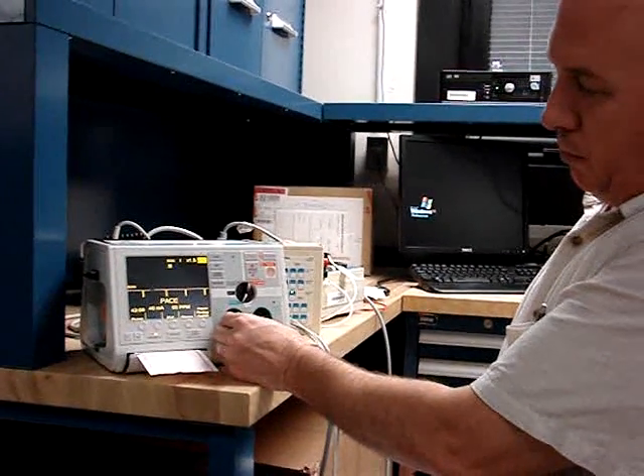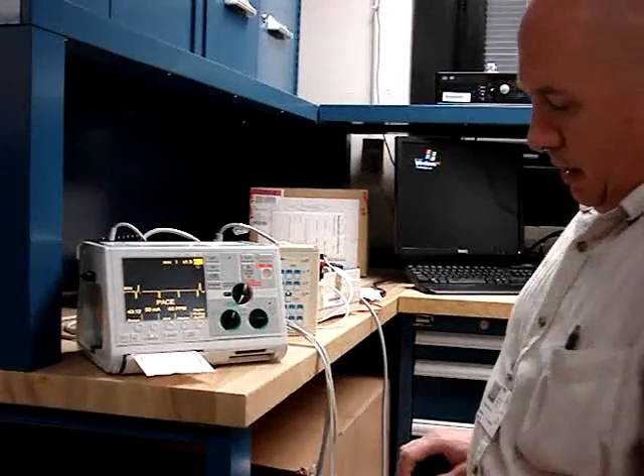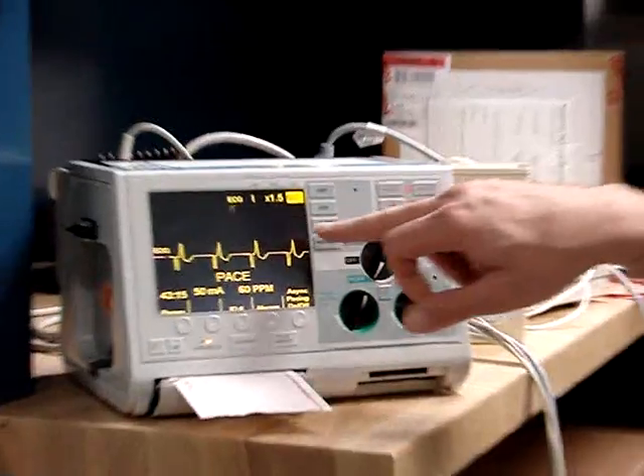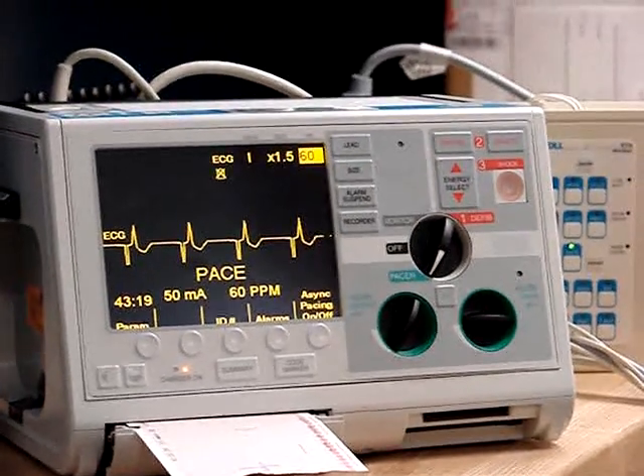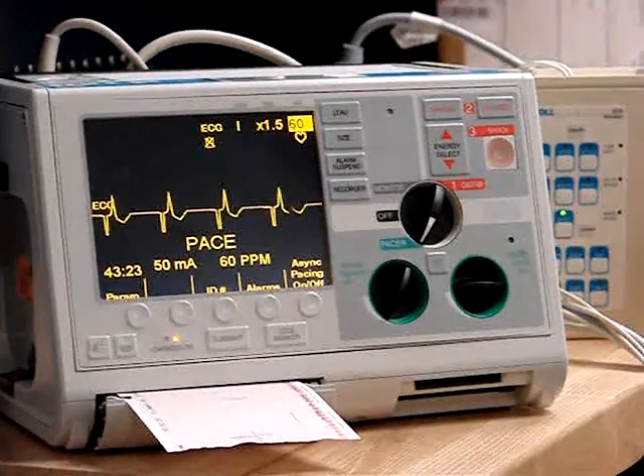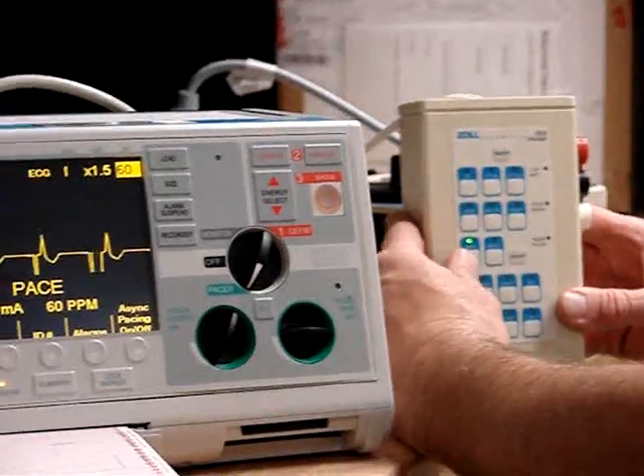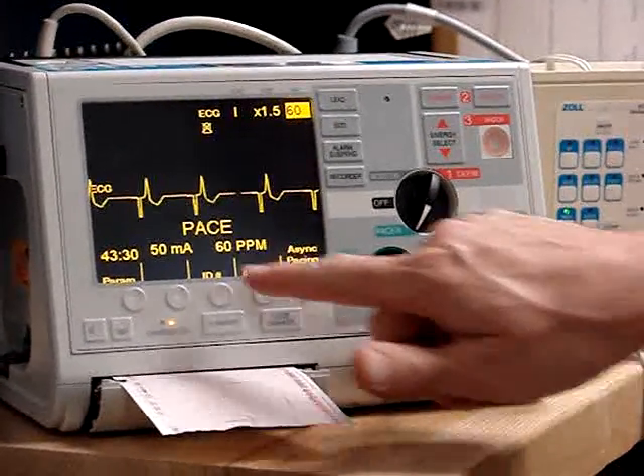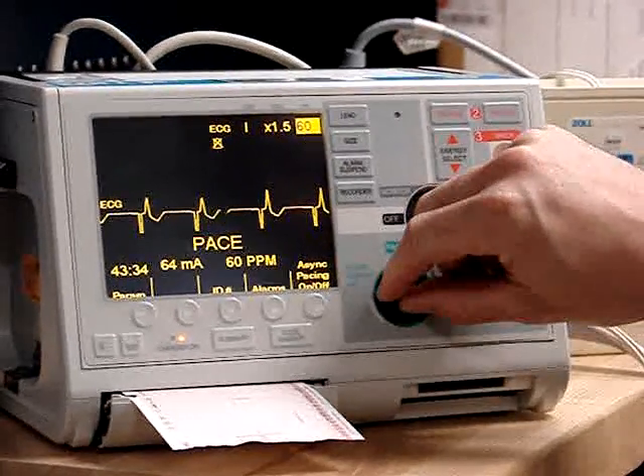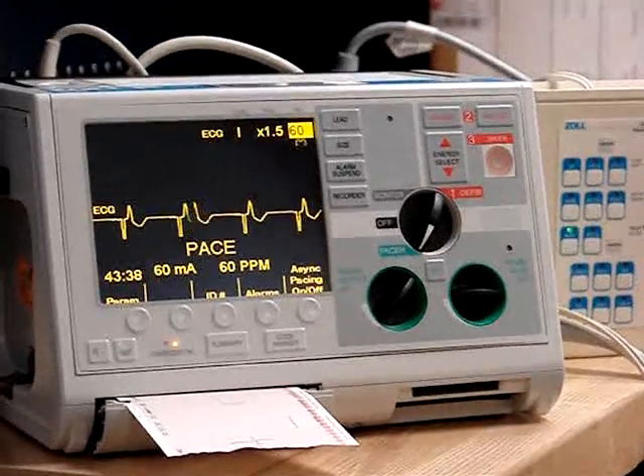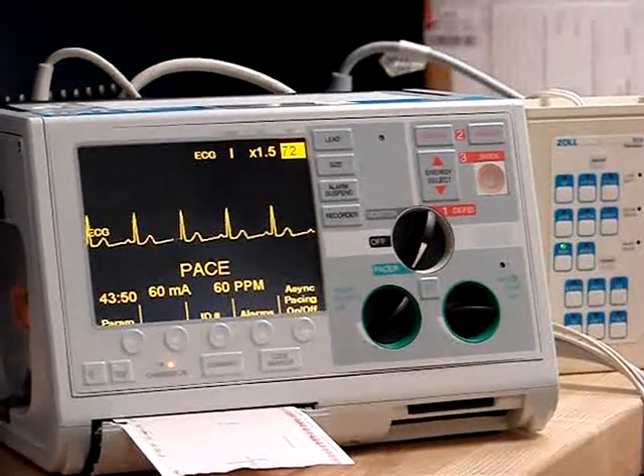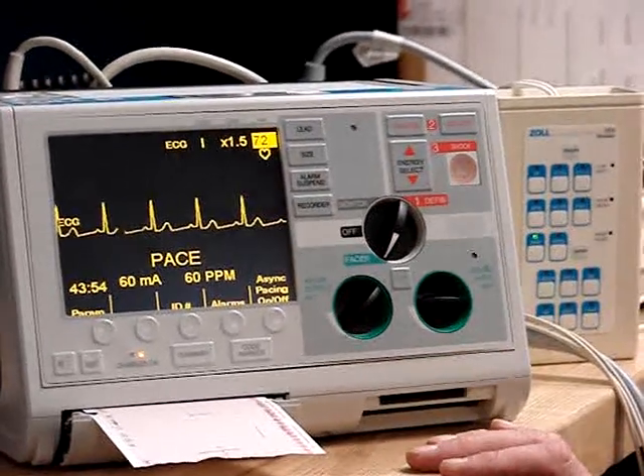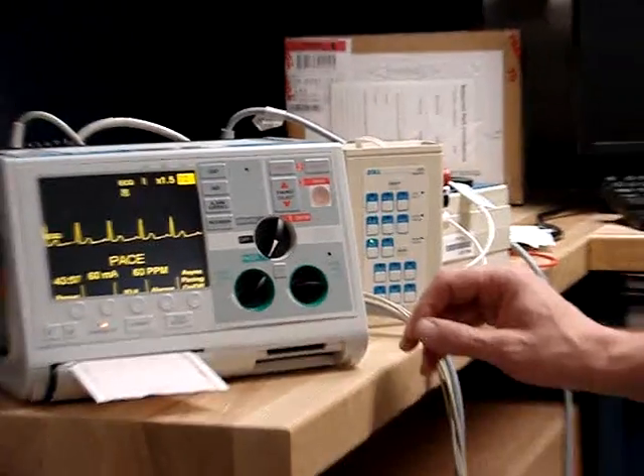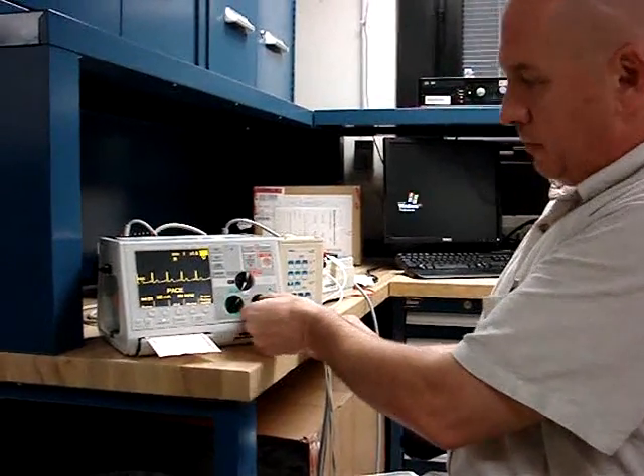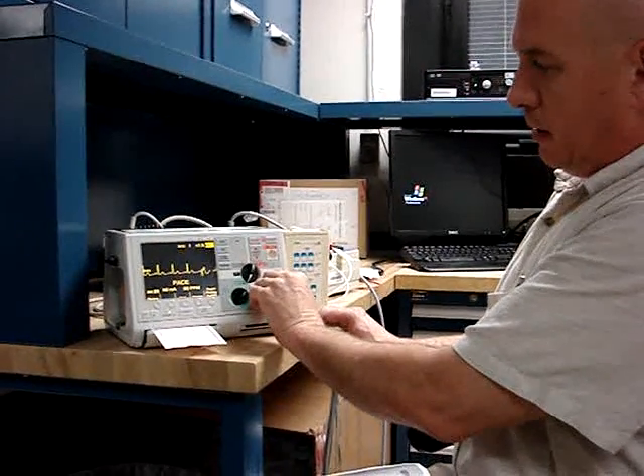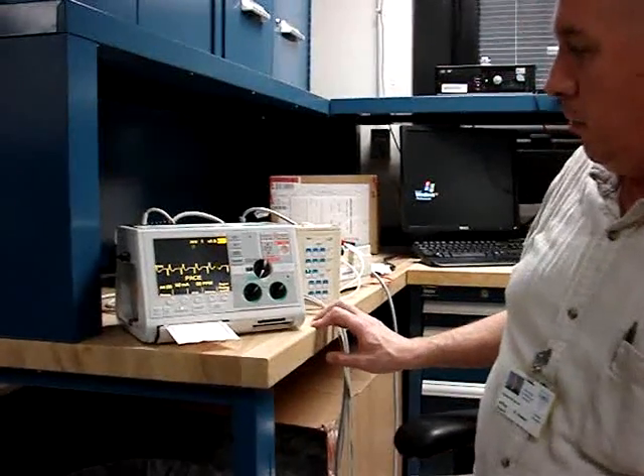As we set the pacer output to 50 milliamps, now we'll get the pacer pulse and the capture, pulse capture. So after that, our next step is to go back to the normal sinus rhythm. And we need to be at 60 milliamps and 60 ppm. Okay, now we're only getting the pulse capture. Okay, now we need to bring the ppm to 80. Now we're getting the pacer and pulse capture.